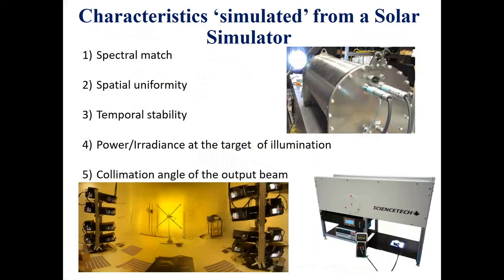So to sum up, what makes a solar simulator different from a light source is its ability to mimic solar light. There are a few main characteristics that we must consider, and these characteristics are standardized for different testing applications. The solar simulator should be able to produce a close match to the sun's spectrum. It should produce a spatially uniform area of illumination, just as the sun does. It should also produce a steady output over a standardized period of time. Optionally, the simulator should be able to give the same power density at the illumination area as the sun. Some applications require the light beam to be highly collimated, so our solar simulators can produce such illumination as well. Let's look at these characteristics in detail.